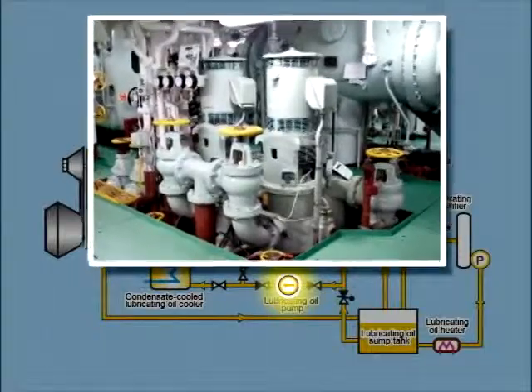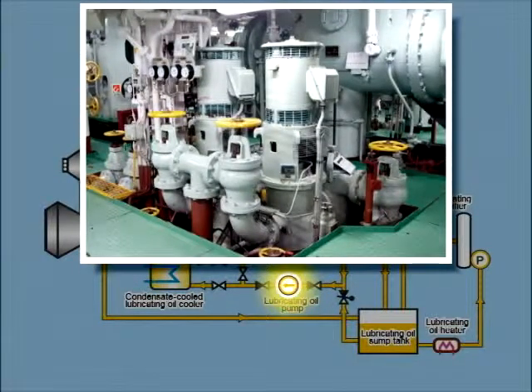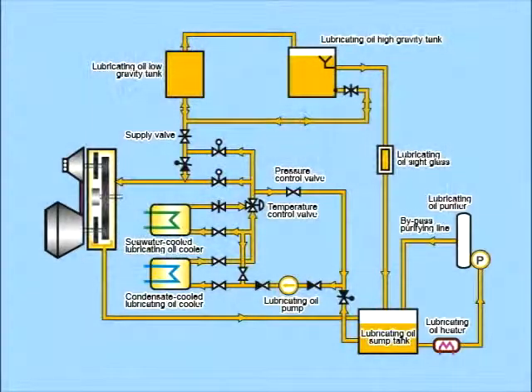Should the main LO pump stop due to a blackout, the LO gravity tank ensures lubricating oil supply for a certain period of time.